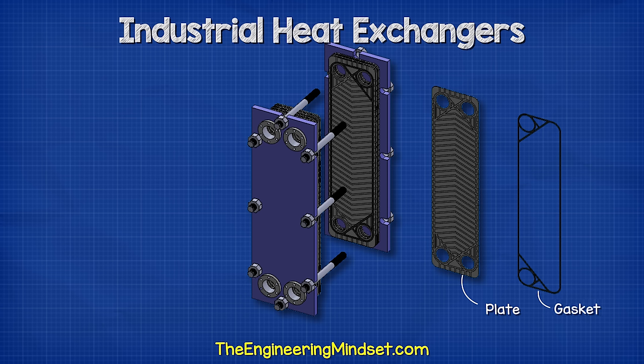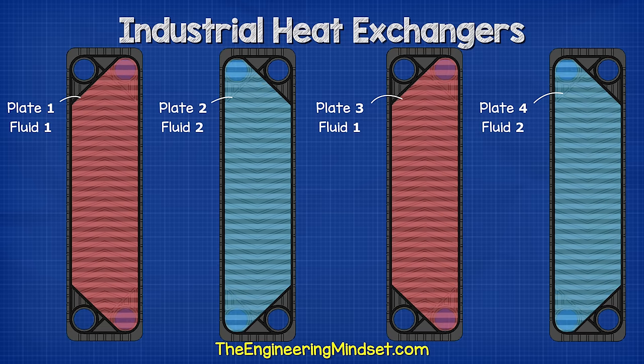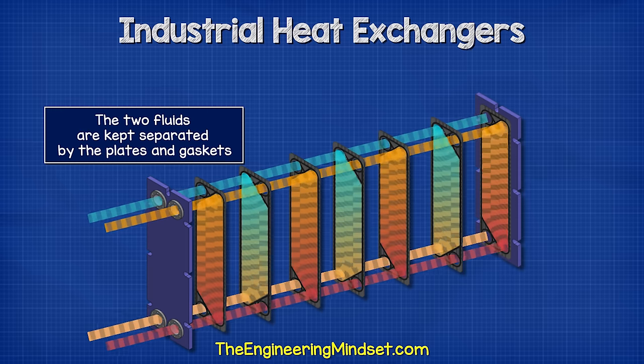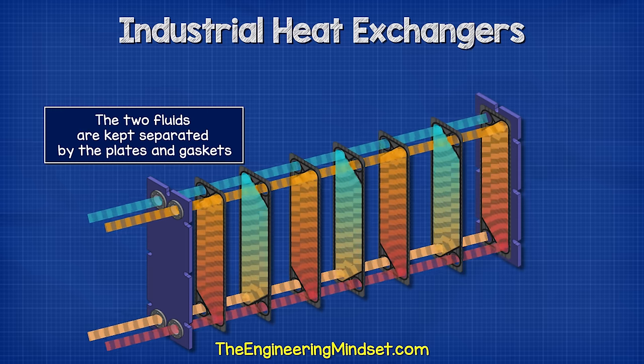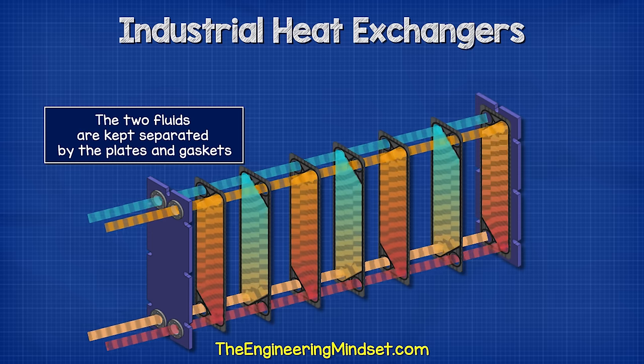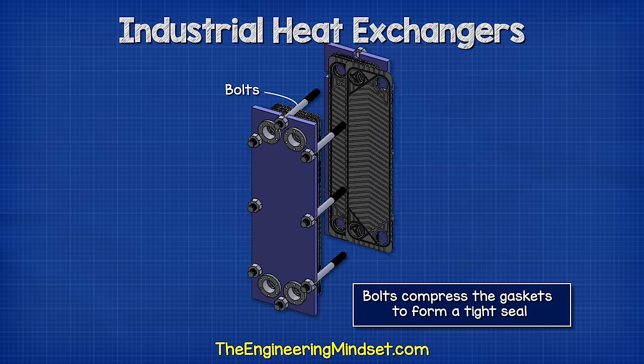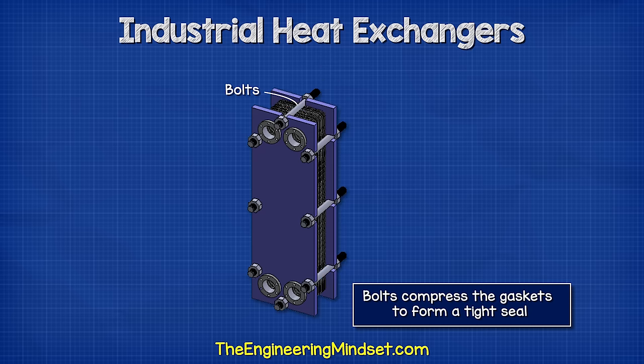The gaskets separate the plates, creating a thin channel between them through which fluid flows. On each plate, the gasket blocks two of the four ports, meaning only one fluid can enter and exit. The next plate allows the second fluid to pass. This alternates throughout the heat exchanger, keeping the two fluids completely separated — only thermal energy flows through the sheets. The entire unit is held together with long bolts, which compress the gaskets to form a very tight seal.